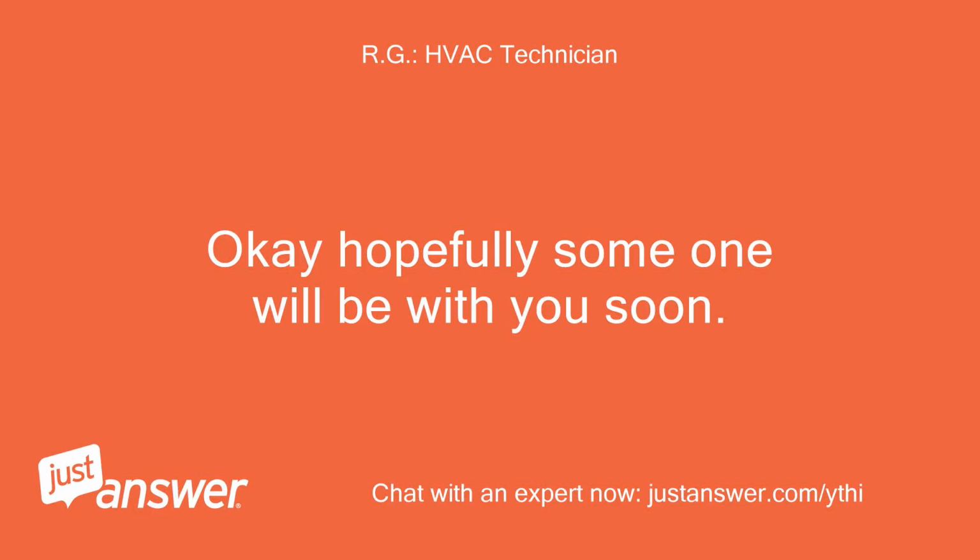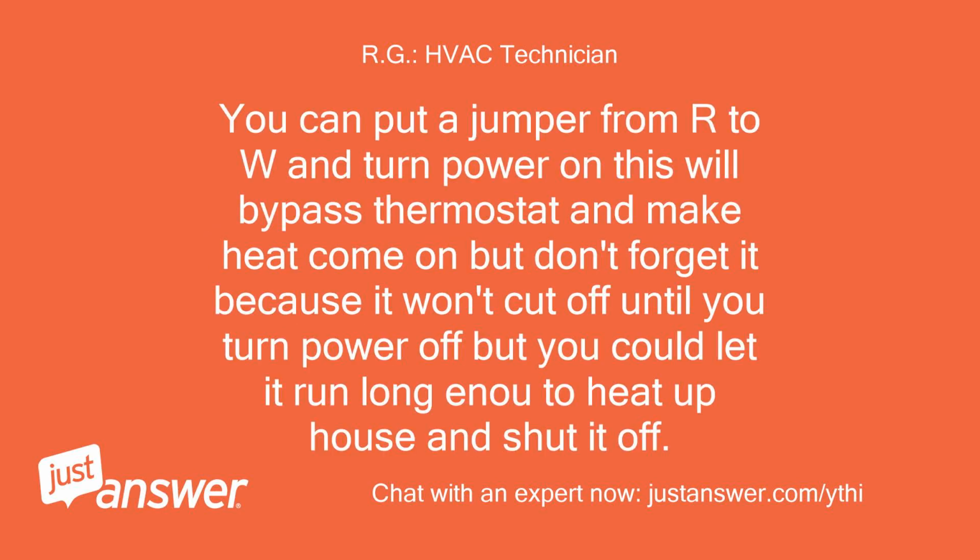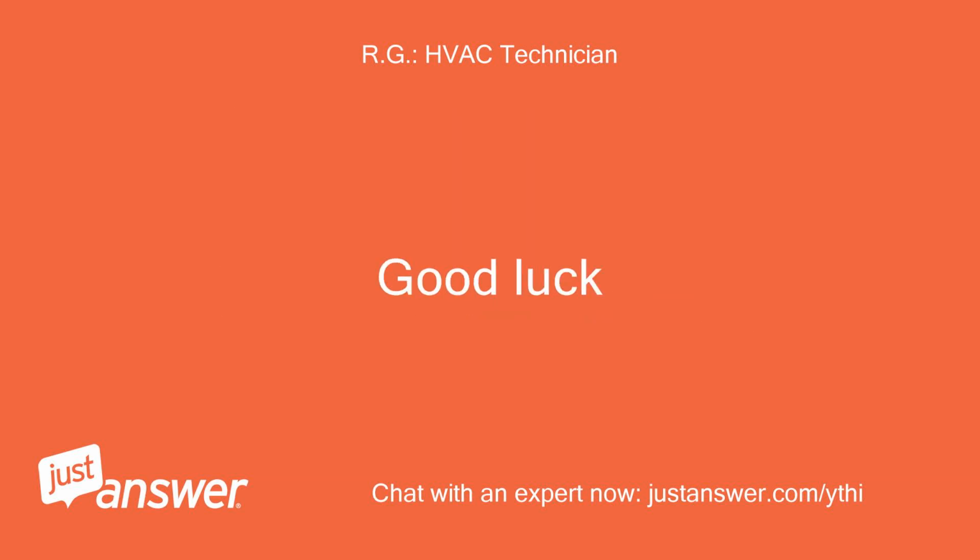Okay, hopefully someone will be with you soon. You can put a jumper from R to W and turn power on. This will bypass the thermostat and make heat come on, but don't forget it, because it won't cut off until you turn power off. But you could let it run long enough to heat up the house and shut it off. Good luck!